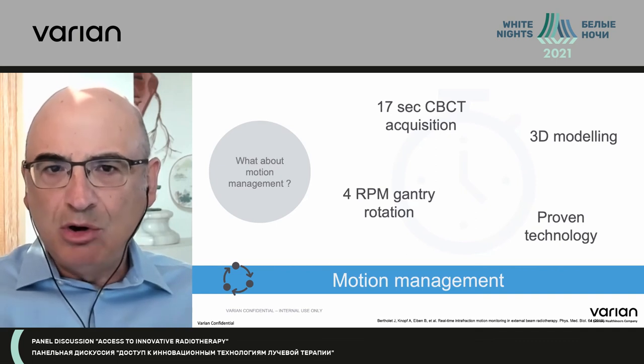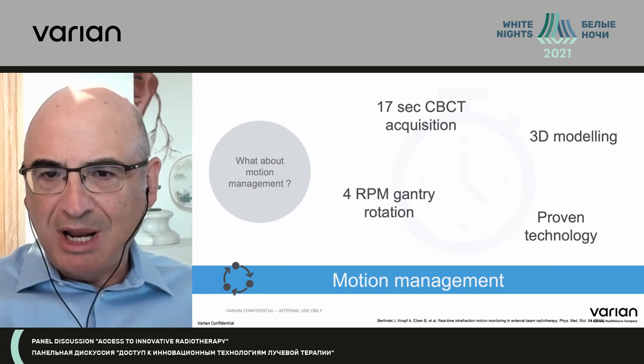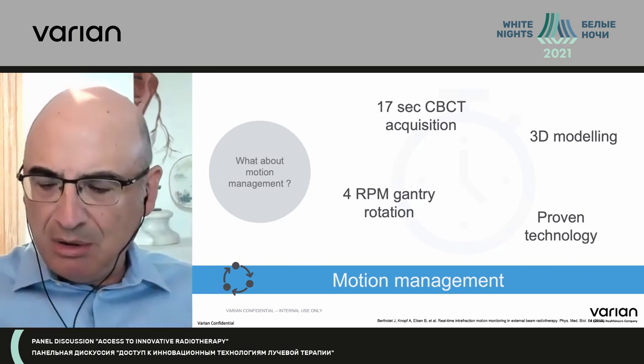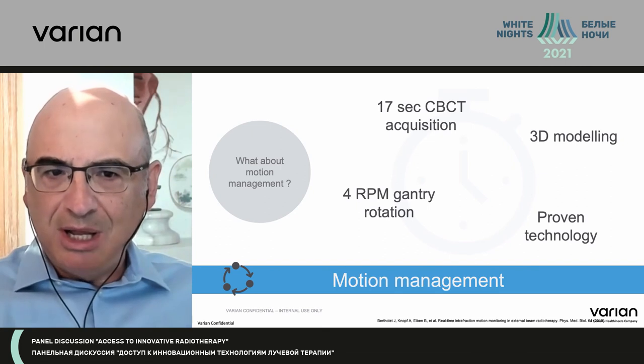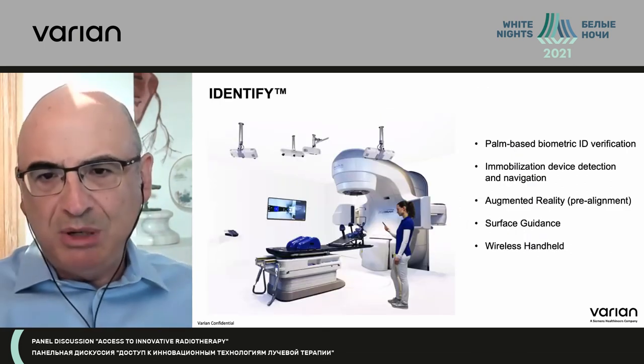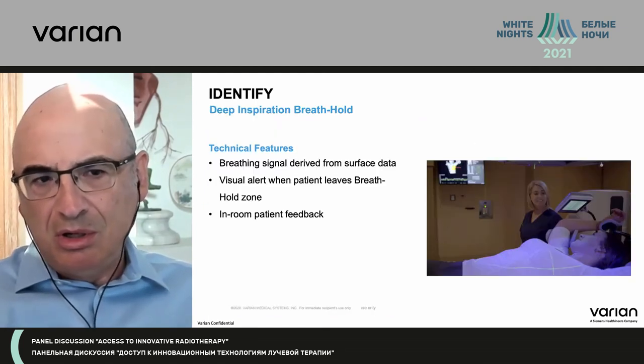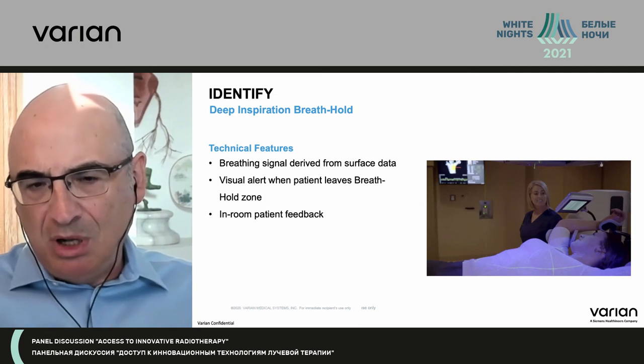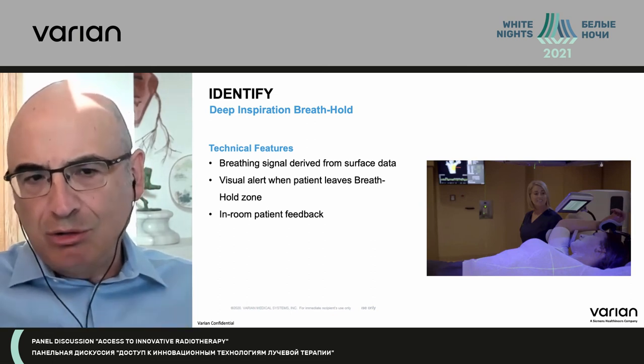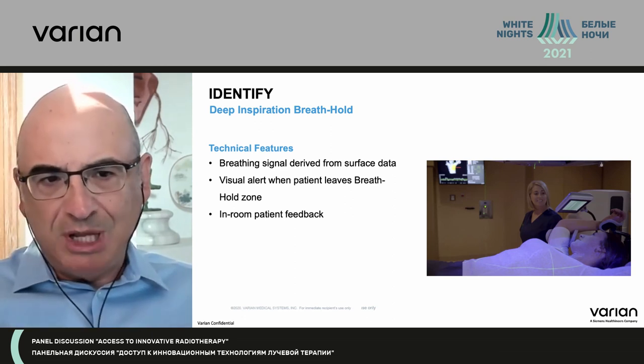We have to remember that the cone beam acquisition is very quick — it's a 4 RPM gantry rotation during imaging. A lot of what we do in traditional radiotherapy doesn't apply here. For motion management, the system is very well built for doing breath hold. So instead of gating or tracking, breath hold is a very efficient solution on this platform.